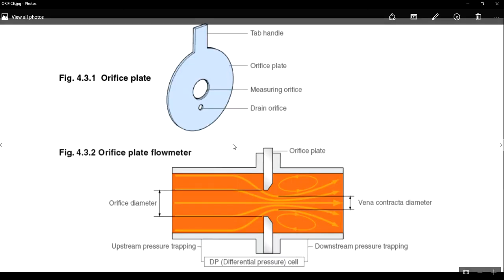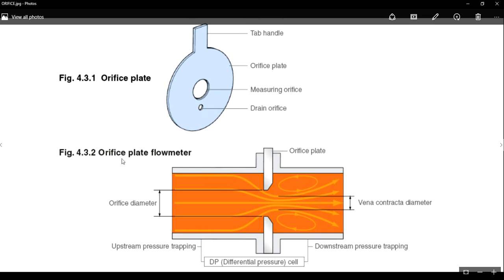Now you can see a glance at this image wherein you can look at the orifice plate representation. This is an orifice plate — it has a tab handle and this is the circular section which is called the orifice plate, and it has got certain thickness. The thickness may vary from 0.8 to 1.6 mm. In between you will find an opening provided — a hole provided in the center of this plate. Just below this opening you will see a small hole used for draining purpose as well.